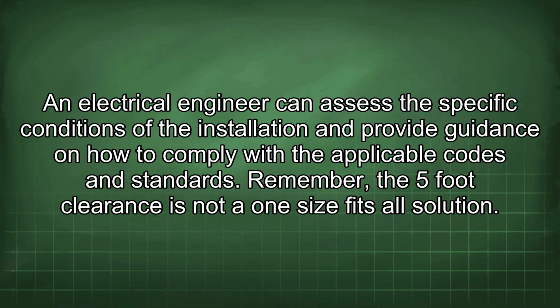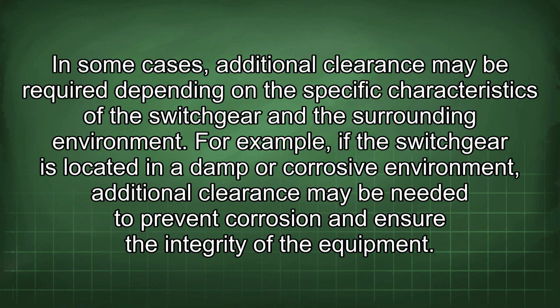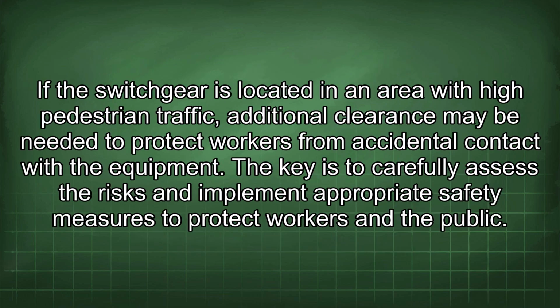Remember, the 5-foot clearance is not a one-size-fits-all solution. In some cases, additional clearance may be required depending on the specific characteristics of the switchgear and the surrounding environment. For example, if the switchgear is located in a damp or corrosive environment, additional clearance may be needed to prevent corrosion and ensure the integrity of the equipment. If the switchgear is located in an area with high pedestrian traffic, additional clearance may be needed to protect workers from accidental contact with the equipment.